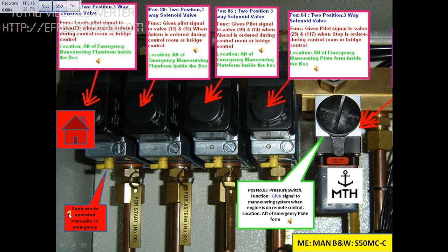In case there is a malfunction of these solenoid valves number 90, 88, 86, and 84, that is there is an electrical malfunction and the solenoid valve is not working, these valves can be operated by a knob provided on these blocks which is shown in the picture.